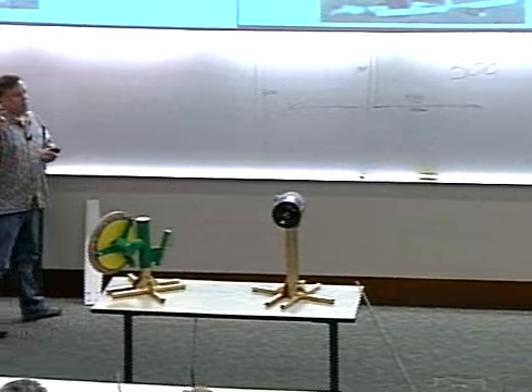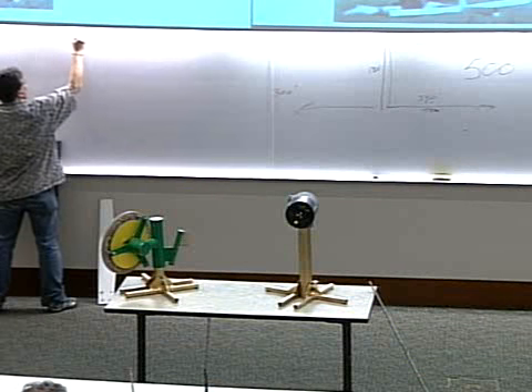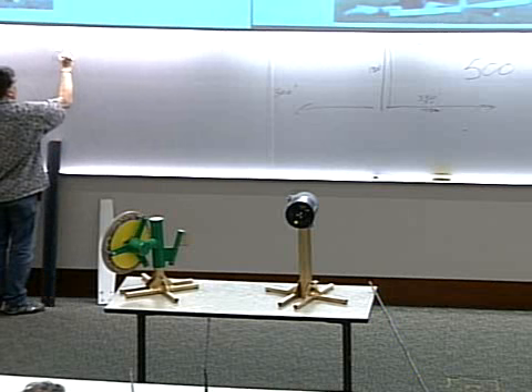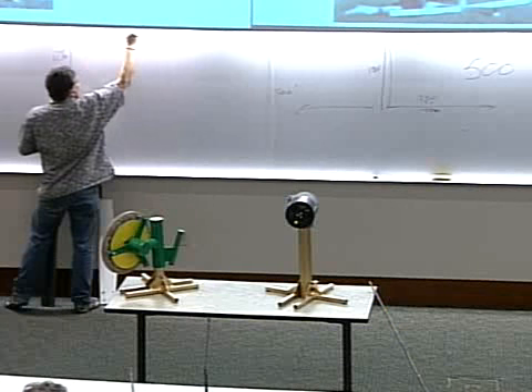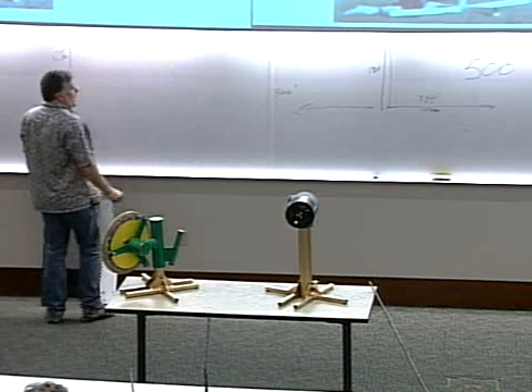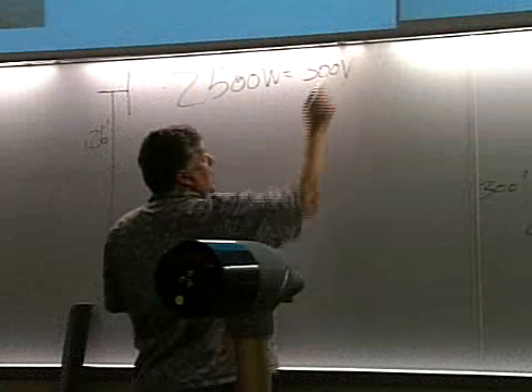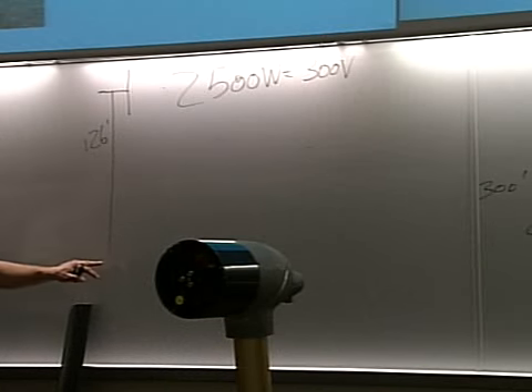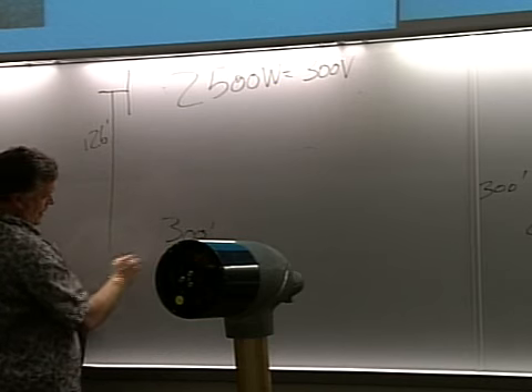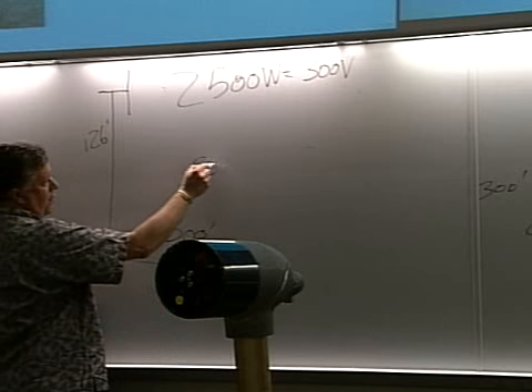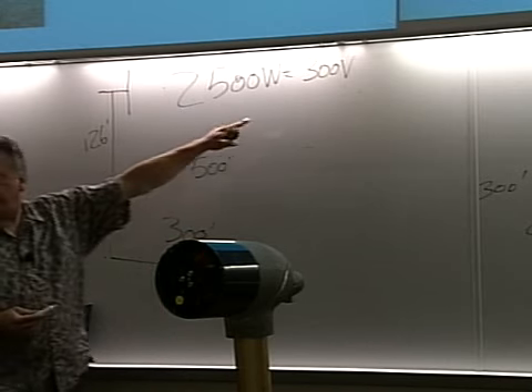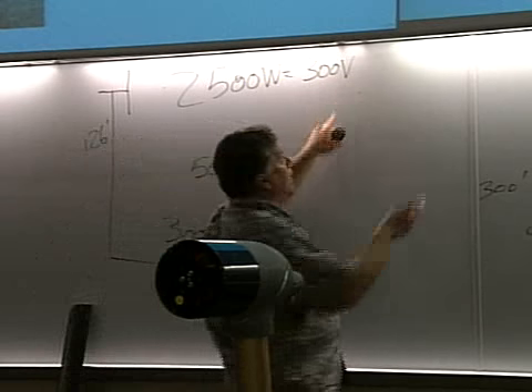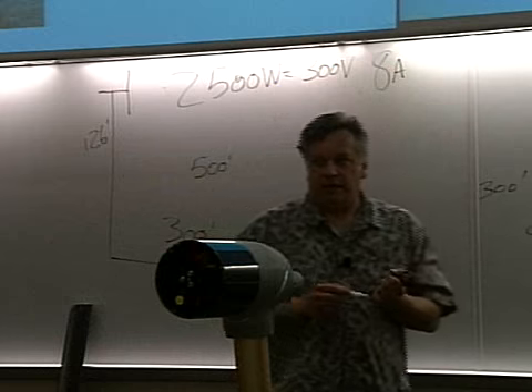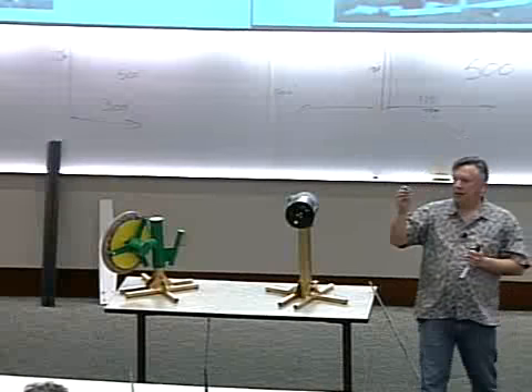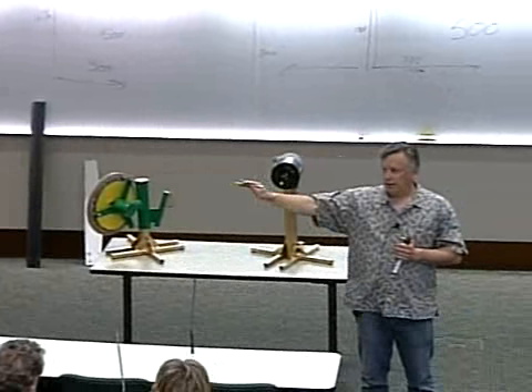Okay, here's another installation. Same machine, but wired in a high voltage configuration. We have a 2,500 watt Proven on a 126-foot tilt-up tower, 2,500 watts, running at 300 volts, wild AC. So we're coming down 126 feet, and then going over about 300 and some feet to the balance of systems. So let's say 500 feet again. How many amps is it going to be running at? About 8 amps. What's the conductor size? Infinitely smaller. Now we're looking at maybe a number 6 or so coming over from the tower top all the way down and over to the balance of systems.